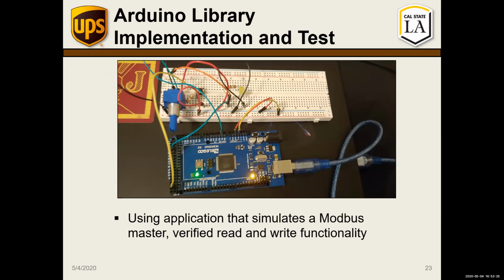This was my test bed, and my procedure was as follows. To test read functionality, I had a potentiometer for an analog input, so we could read the resistance level, and a button for a digital input. Using an application that simulates a Modbus master, I was able to write to any of the pre-configured registers on the Arduino Mega. If a value went above a certain number, it would blink an LED. That was successful, and this implementation was ready to go.